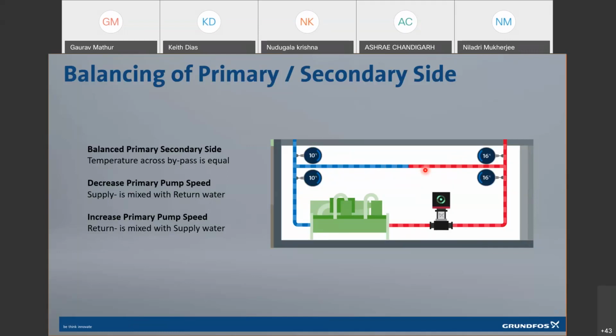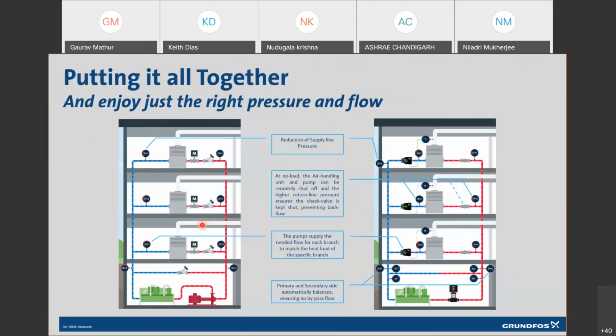And that actually simplifies the system. What we essentially see is that if the flow on the primary side is higher and the temperature which is going back to the plant room is going down, then you need to decrease the primary pump speed. In the opposite direction, when your load is increasing and the requirement of chilled water is building up, the temperature is rising on the building side. And under that condition, you have to increase the primary pump speed. That simple is the control which is possible with the help of distributed pumping.